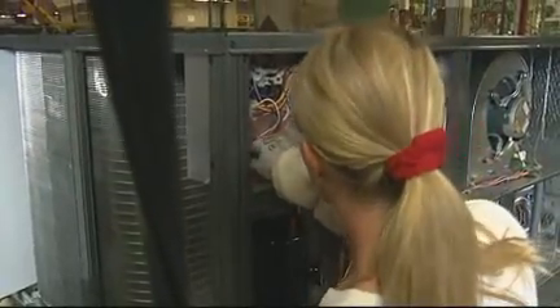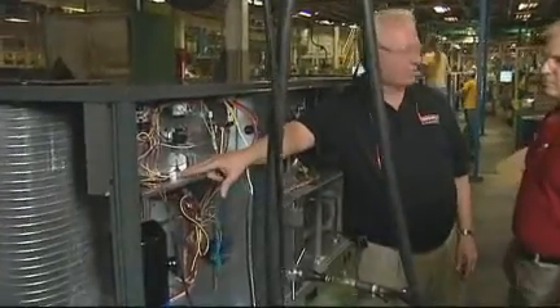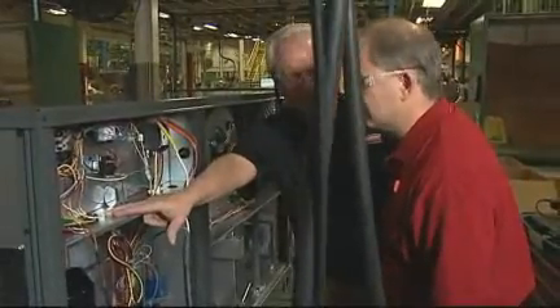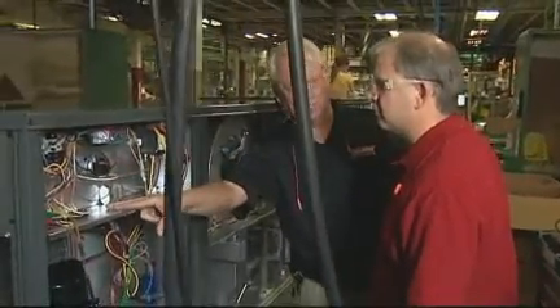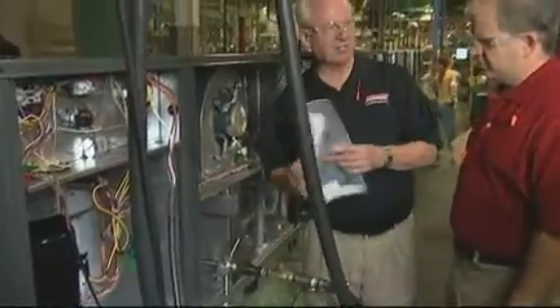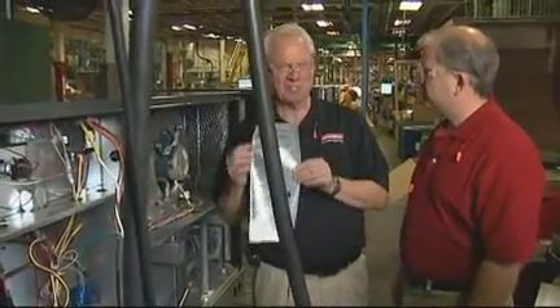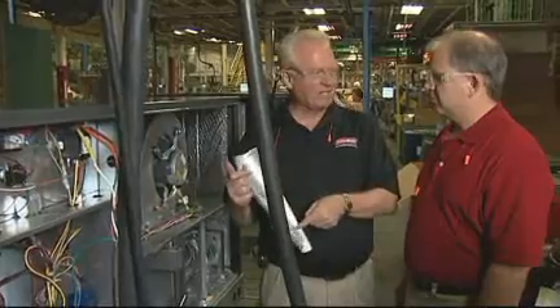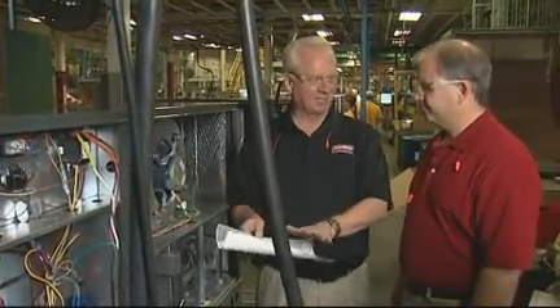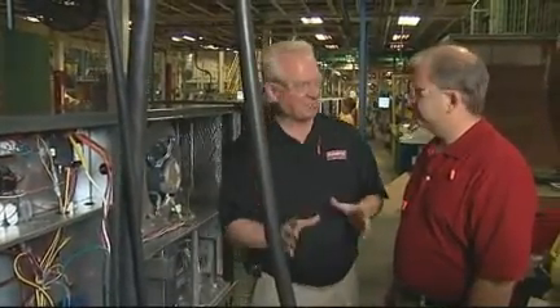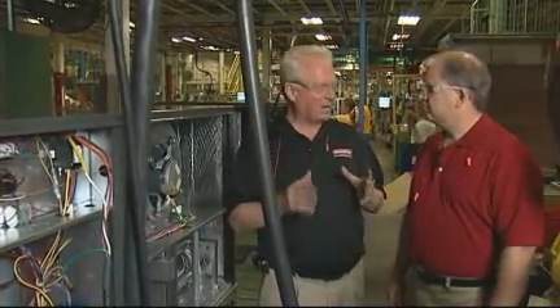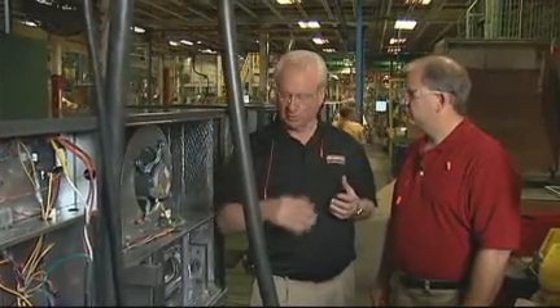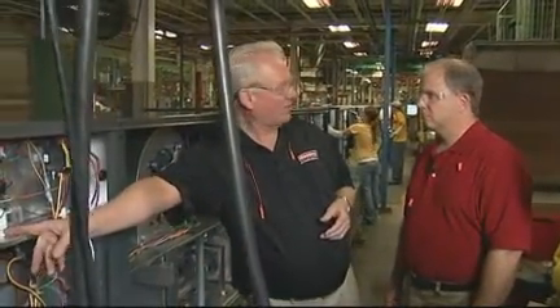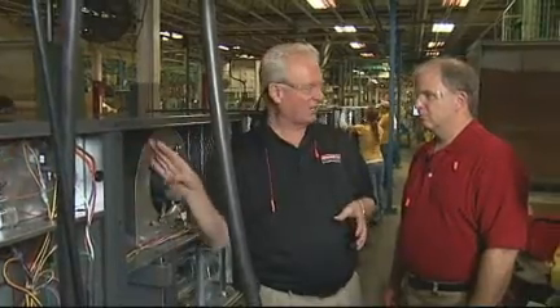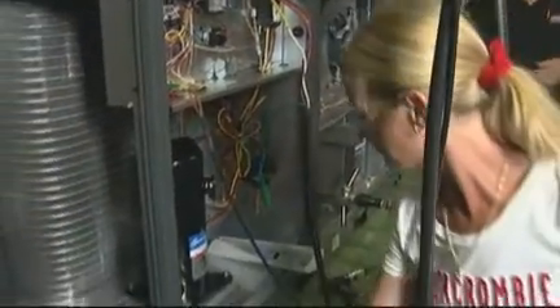Let me point out one thing before she starts the run test. You see this label that we put inside the control box? Yes. That has the model number and serial number. This serial plate that goes on the outside, after 10 years of sunlight, you can't read that. Right. I don't care what label there is, by what manufacturer. Our customers told us it's very important that they are able to identify the model and serial number of the unit no matter how old the unit is. So we responded, and we put a little sticker that's got the model and serial number inside the control box where it'll never be wiped out by sunlight.